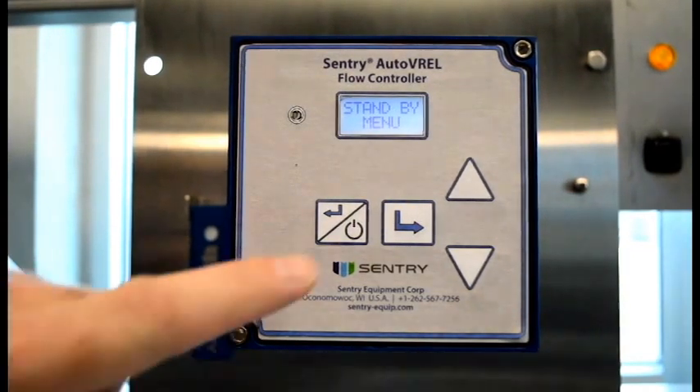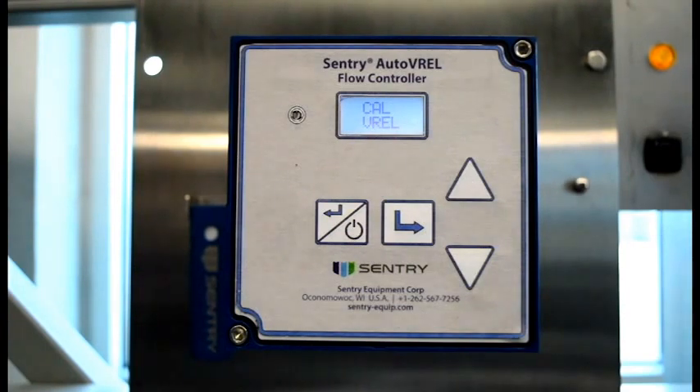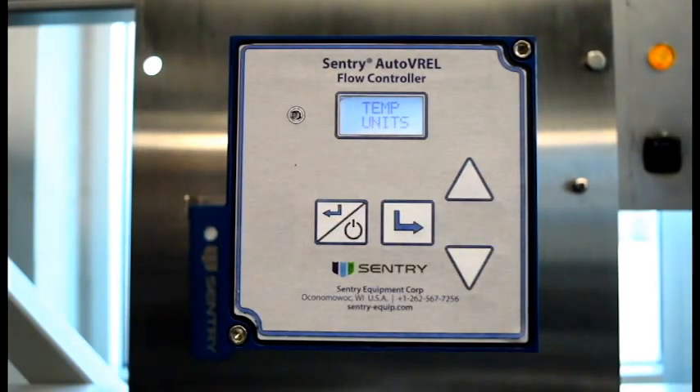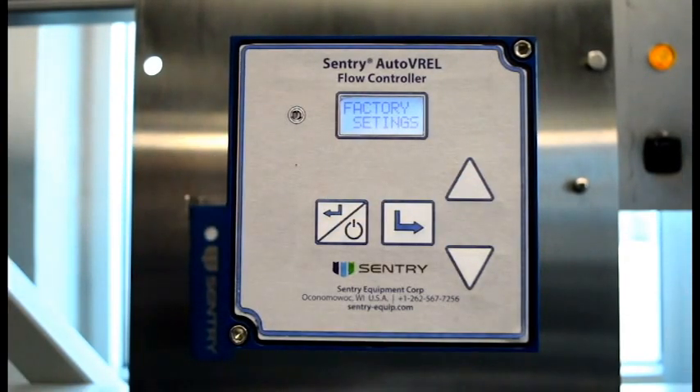Once in standby, depress the Enter key to get into setup. Once in setup, there are three options: Cal VREL, which calibrates the VREL with the flow meter; Temp Units, which changes between Celsius and Fahrenheit; and Factory Settings, which is available for factory personnel only. Once the appropriate screen is showing, depressing the Enter key will enter that setup mode.